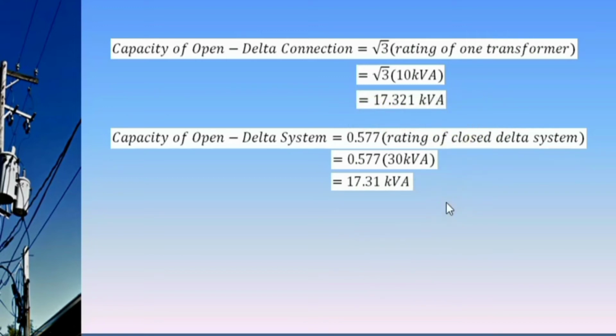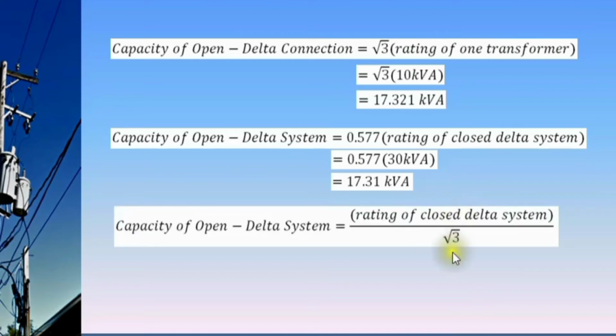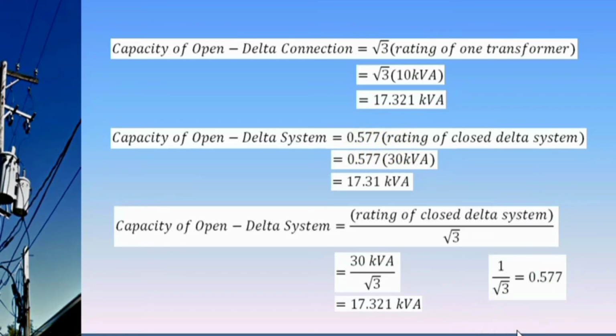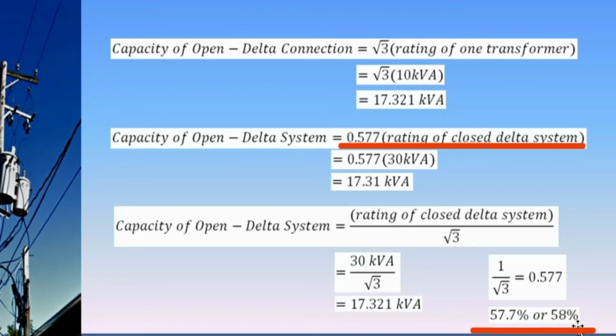Still another way is to divide the rating of the closed delta system by square root of 3. So again, if the rating of the closed delta system is 30 kVA, divide that by square root of 3, this will give us 17.321 kVA. The 0.577 in this equation is taken from 1 over square root of 3. That's why the capacity of the open delta is 57.7%, or that is 58% of the capacity of a closed delta system.